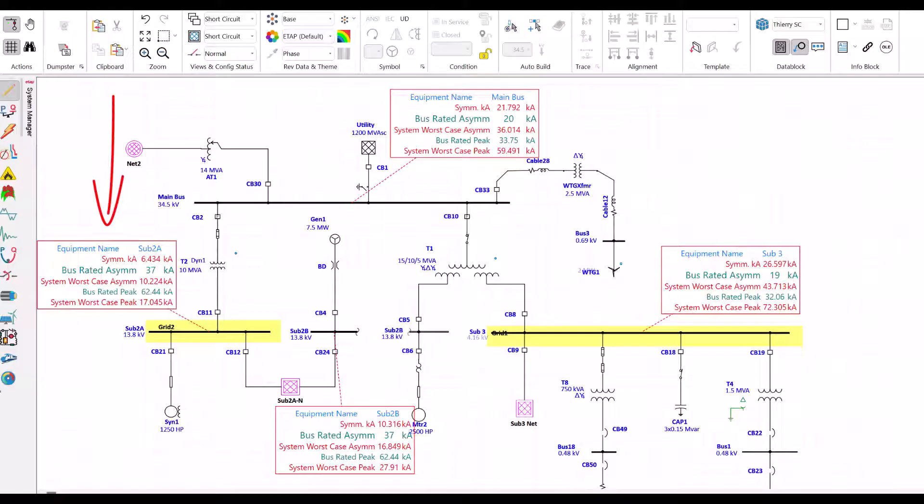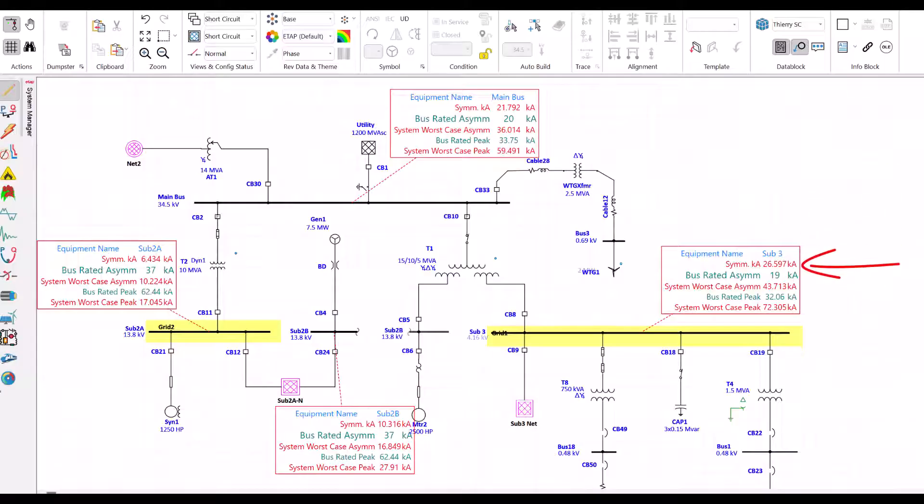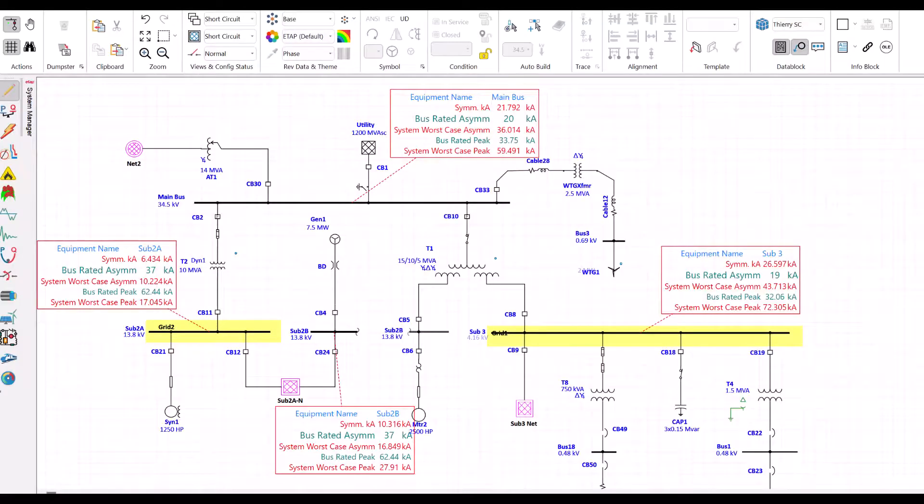Let's look at sub 2A. The bus is rated for 37kA and the system can produce 10.2kA. No issue - 37kA is greater than 10.2kA. Sub 2B: bus is rated for 37kA, the system can produce 16.8kA. No issues. Sub 3: the bus is rated for 19kA and the system can produce 43kA. Not good. We have an issue - 19kA is less than 43kA. We are done. Now the audience has a better grasp of what short circuit studies do. I can now influence them without authority to try to solve the findings.